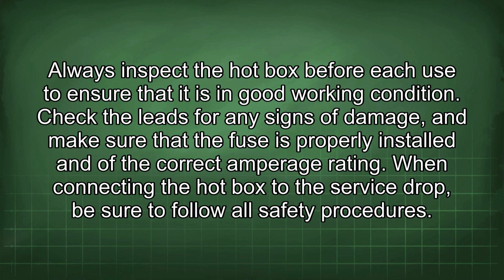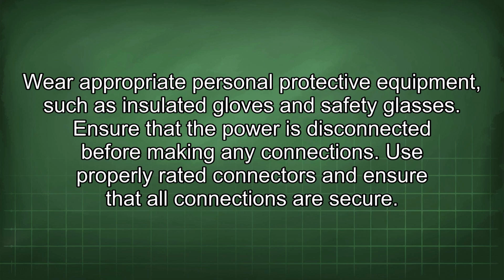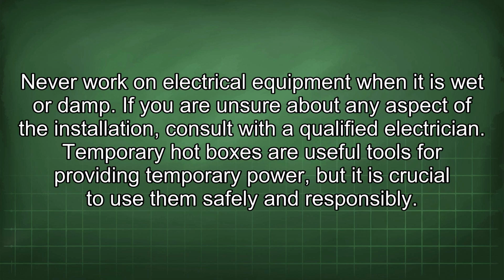Check the leads for any signs of damage, and make sure that the fuse is properly installed and of the correct amperage rating. When connecting the hotbox to the service drop, be sure to follow all safety procedures. Wear appropriate personal protective equipment, such as insulated gloves and safety glasses. Ensure that the power is disconnected before making any connections. Use properly rated connectors and ensure that all connections are secure. Never work on electrical equipment when it is wet or damp. If you are unsure about any aspect of the installation, consult with a qualified electrician.